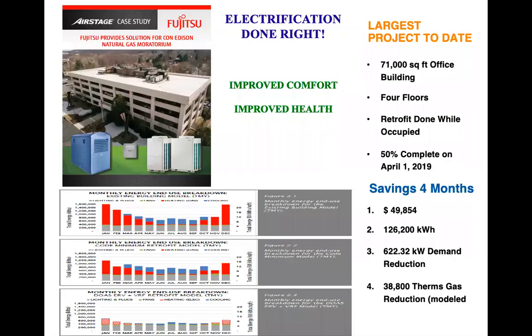But what you'll see there is, in a nutshell, over a 1-year period, with just the last 2 months, the second half of the building, the heat pumps were commissioned and started up. So for the first 10 months, it was just half the building done. And they've realized a $153,000 savings in energy on that retrofit. We had modeled it on that model you see on the bottom graph there at about $70,000 in savings. And we've exceeded the model here.